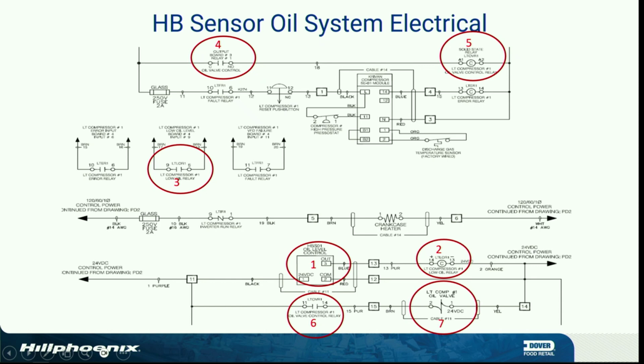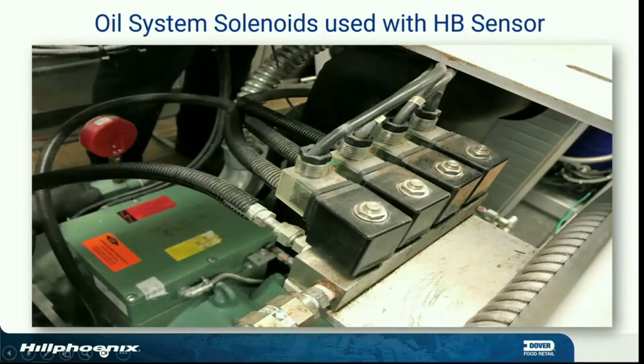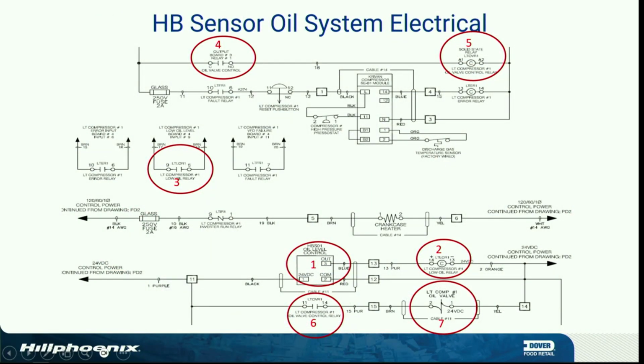A lot of moving parts, huh? So if you're going to troubleshoot this system, look at the wiring diagram and go from beginning to end. If this sensor's red and that one's not lit up, either you got a bad coil or that output leg has failed, and they will. I've seen a couple do it. Not many of them, but a couple. If that's lit up and you don't have your input, then the relay coil is probably fine and the relay points are bad. All right? Follow it through. When you call me, you have the answer for me already. All right?